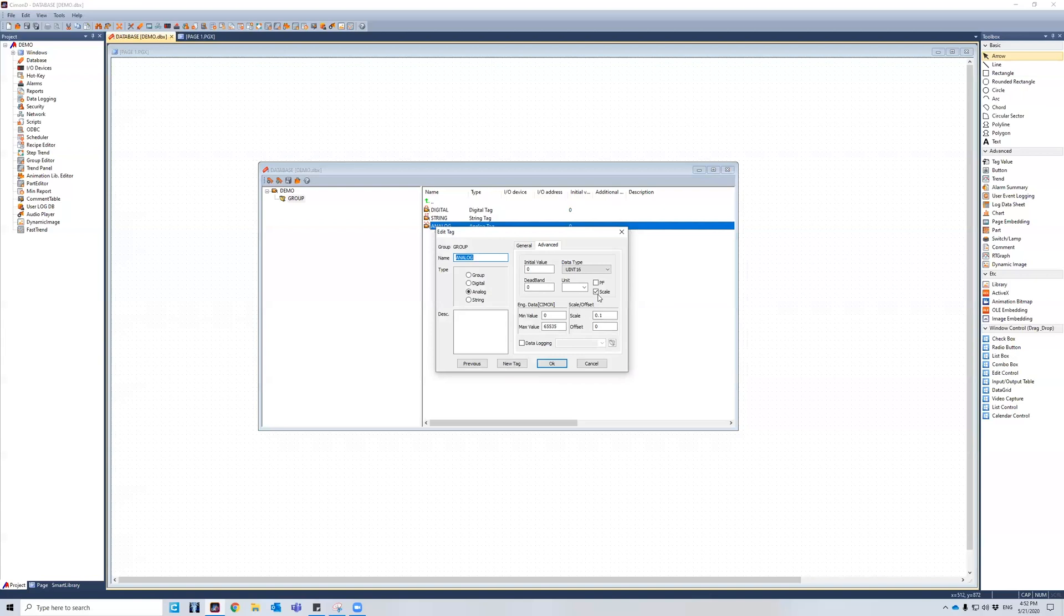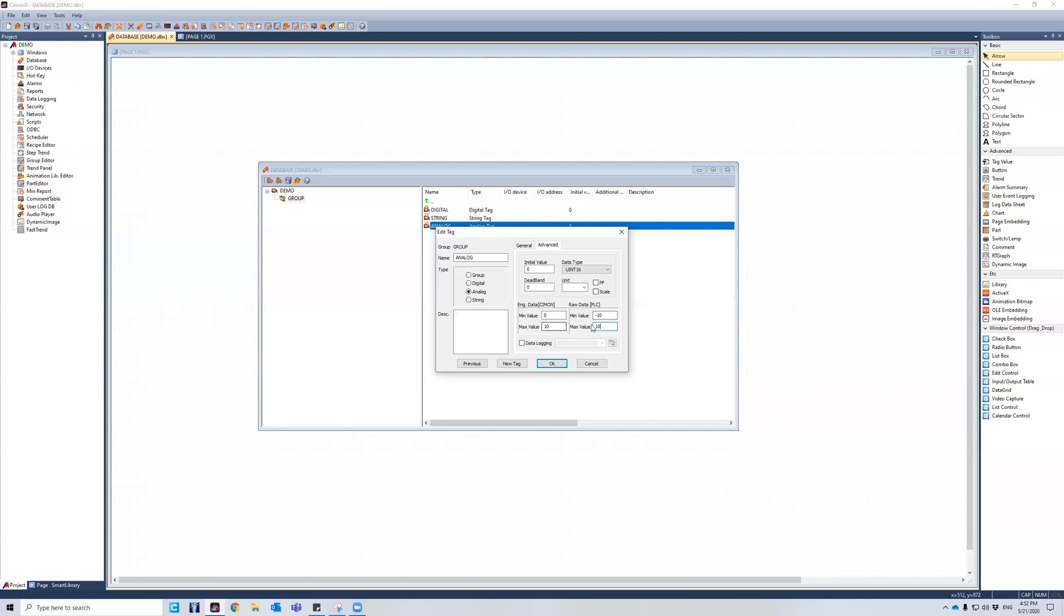So I want to go over a different type of scaling. And it's PLC to SCADA scaling itself. So the SCADA software, if I'm going to put it from 0 to 10, and then the PLC software, I'm going to do negative 10 to 10. And you're going to ask me, well, how does this scaling work? How does it map over? So for instance, the 0 maps to the negative 10. 10 maps to 10 like it should. But it gets tricky when you deal with the numbers in between. So 5 will map to 0 over here. 2.5 will map to negative 5 over here. And 7.5 will map to positive 5 over here. And then that is it for analog.